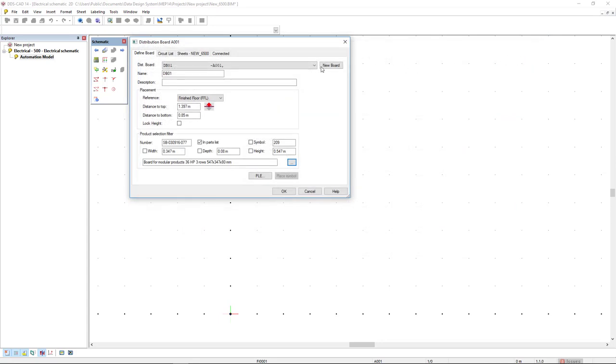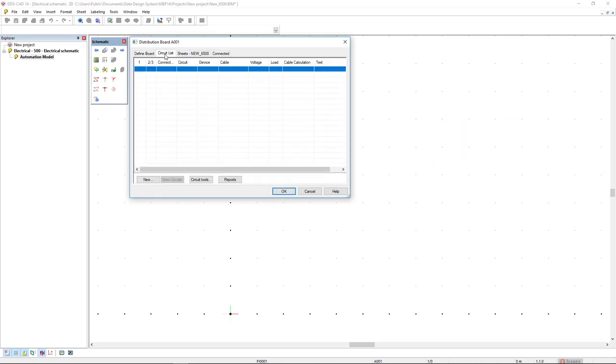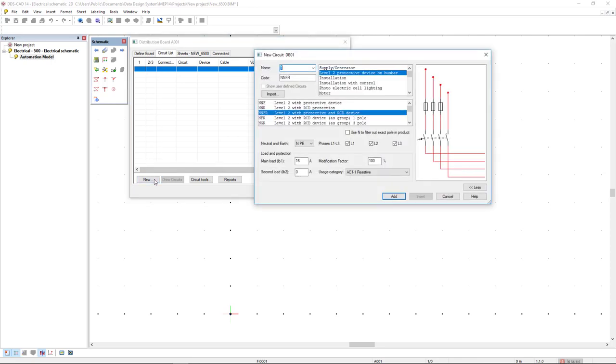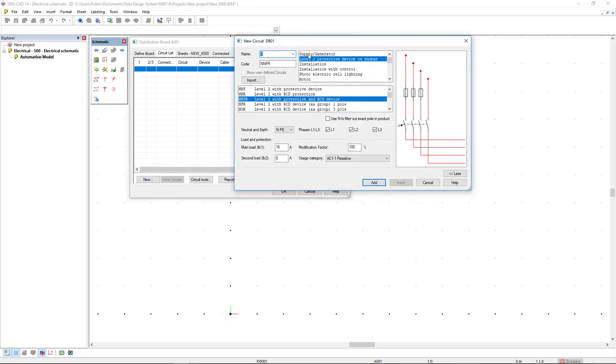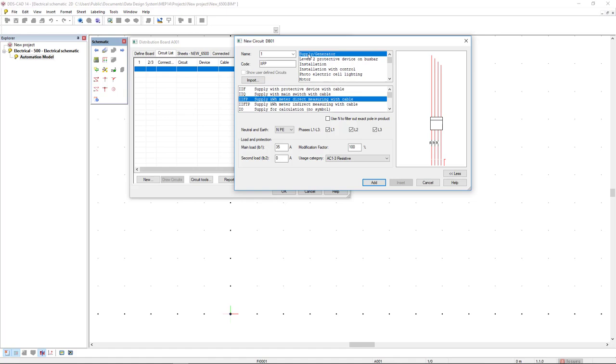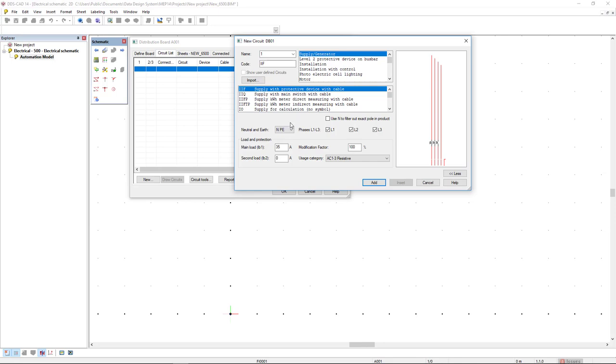Next, I will click on the circuit list tab and define new circuits. I go to the new button and select the category supply generator. I will select the first option, supply with protective device with cable. I will pre-define as 35 ampere and set as three phases and click next add.